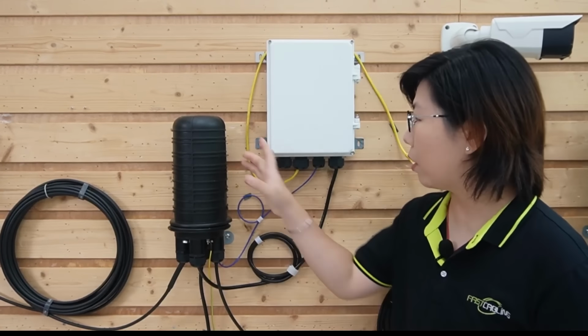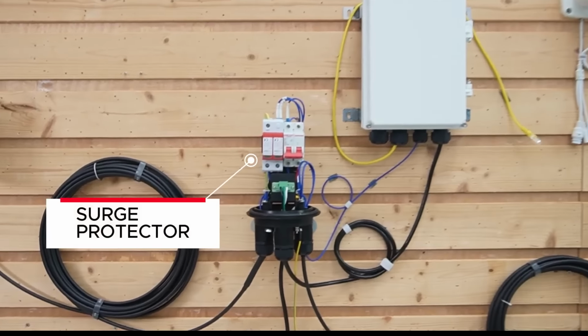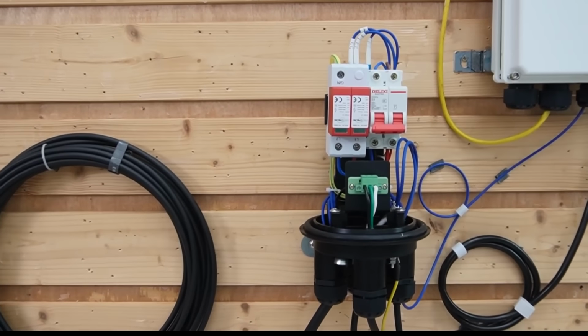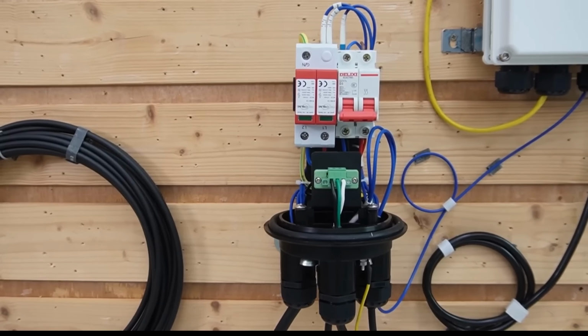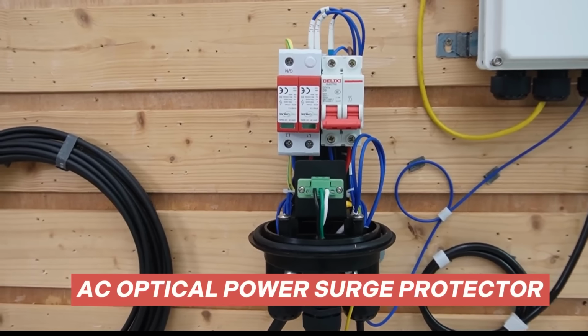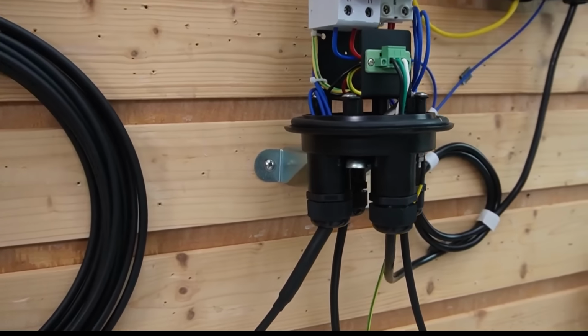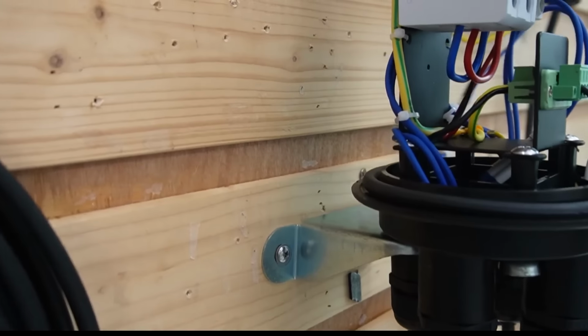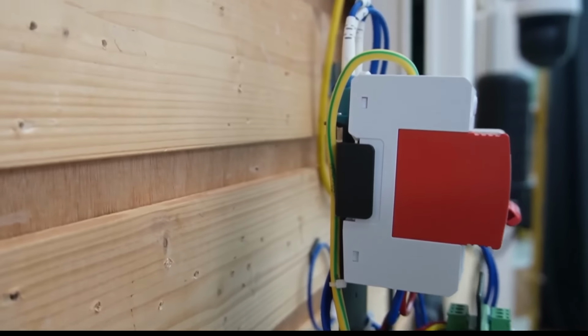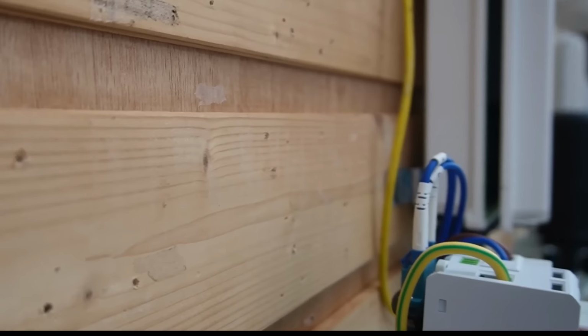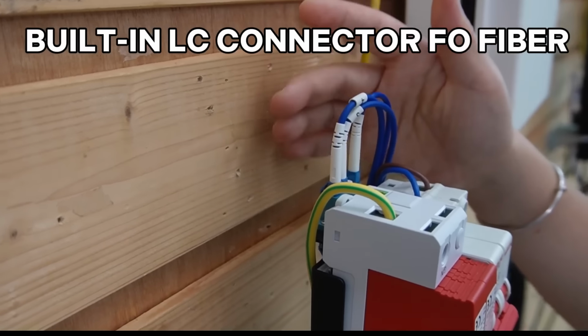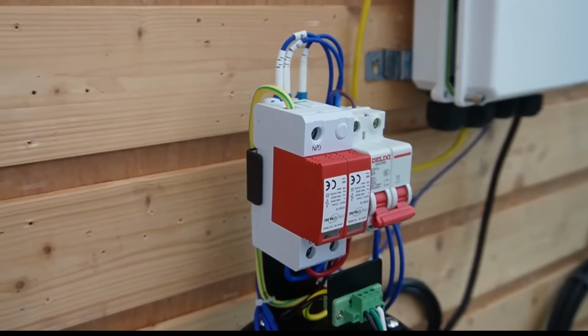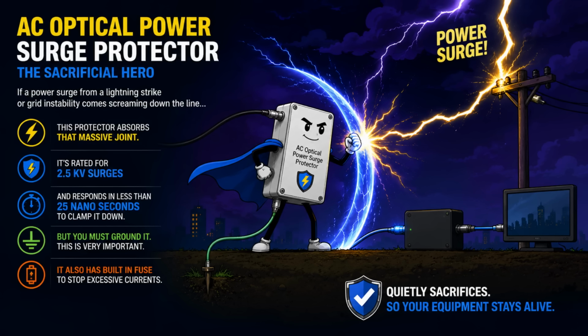At every single one of our 4 locations where we bring in that fiber and connect it to the switch, we must install a surge protector. In our case, since we had AC at each site, we used an AC optical power surge protector. It's housed in a waterproof enclosure because it's living outside. This little box sits between the incoming fiber and the switch, and it has a built-in LC connector for the fiber. Its sole job is to be the sacrificial hero.